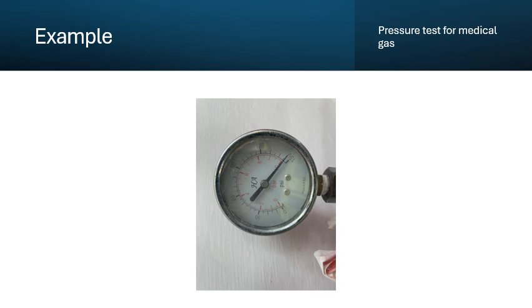Same thing, then you leave it for 2 days. After 2 days, you come back, you open the tape, and you see if it was at the same pressure as 2 days ago. If so, the pipes don't have any leakage, everything is good, and it's ready to be used. If it went down a little, by like 5 psi, or 1 bar went down from 10 bar to 9 bar, then there's a huge problem. They need to check the entire copper pipes of the medical gas system to find where the leakage is.